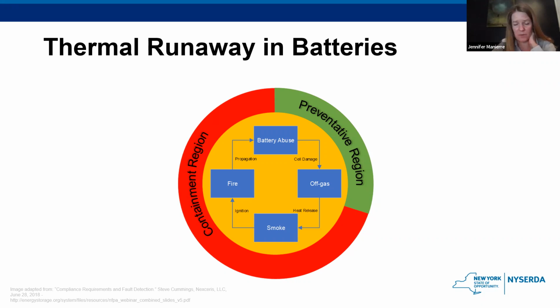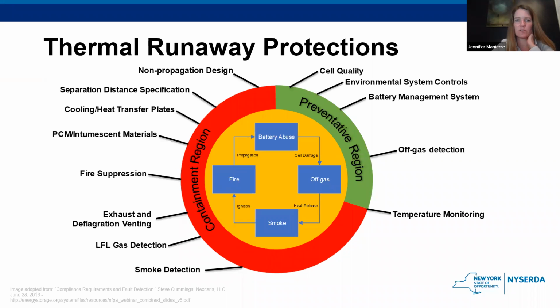So we're moving around to the 3 o'clock section of the chart there. When that happens, we're still considering that to be in the preventative region, the green region. There are things that you can do to prevent it from actually catching fire once it starts off-gassing. If you don't, you're going to start seeing smoke and eventually fire. And now we're in the red containment region, which is larger. So you're not able to prevent the fire from happening anymore, but there are many things you can do to contain it if it is happening. And many of those things are shown here on this slide.